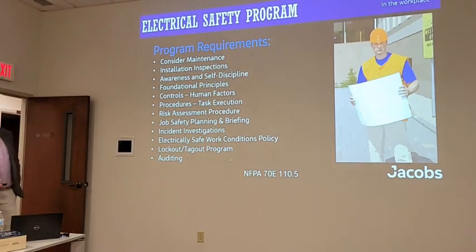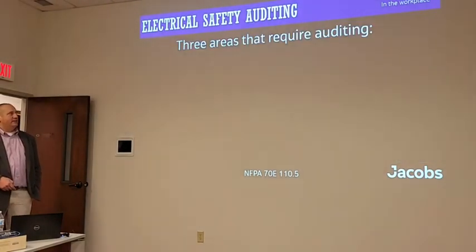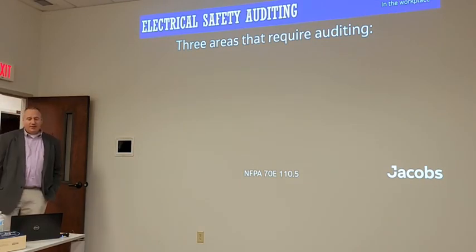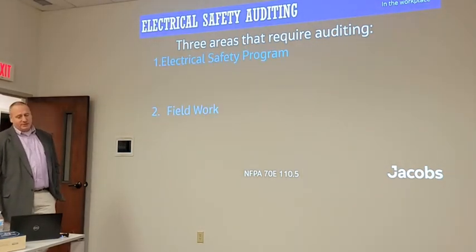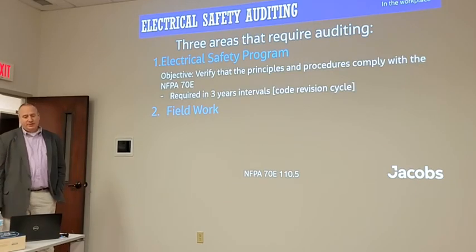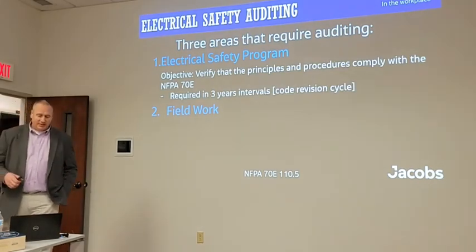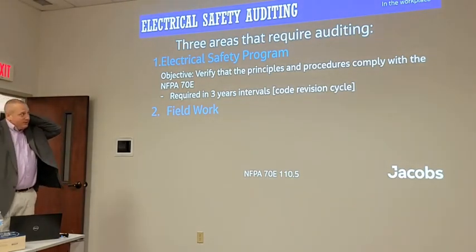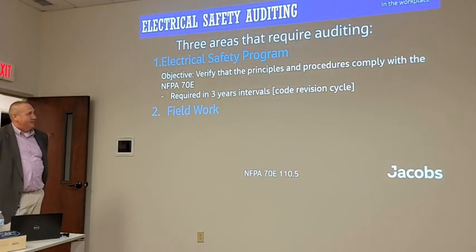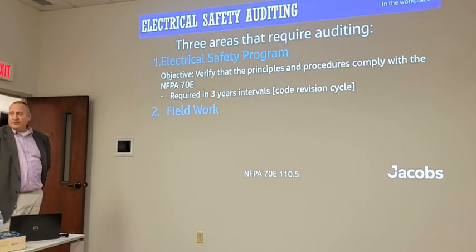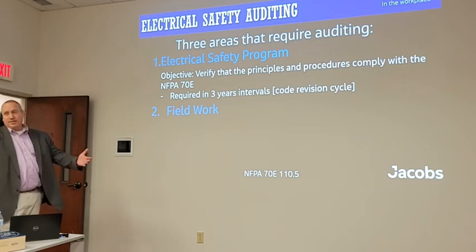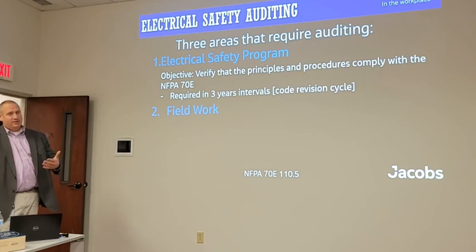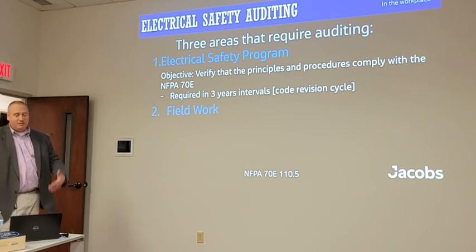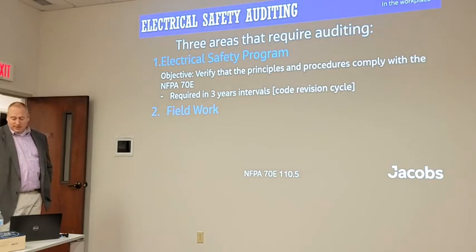Part of that, which is recurring and has to be documented, is audits. There are 3 primary audits that are required. The first one is your electrical safety program audit. The objective there is to verify that the principles and procedures are compliant with the most up-to-date NFPA 70E, which is why they require the program audit to be on a 3-year cycle, because the 70E gets revised on a 3-year cycle. So the intention is the new revision of the 70E comes out, somebody takes that, does an assessment on your program, makes sure that you pick up any of the new things, and everything's still compliant.